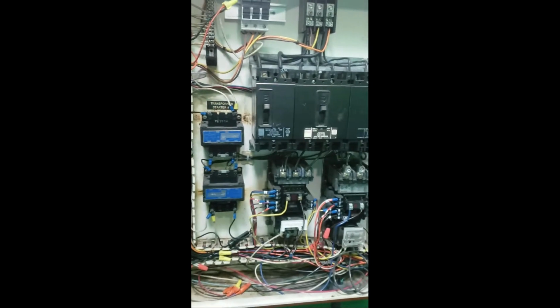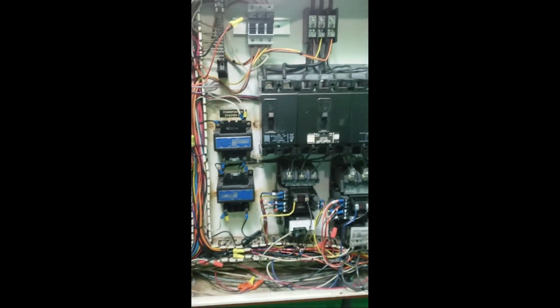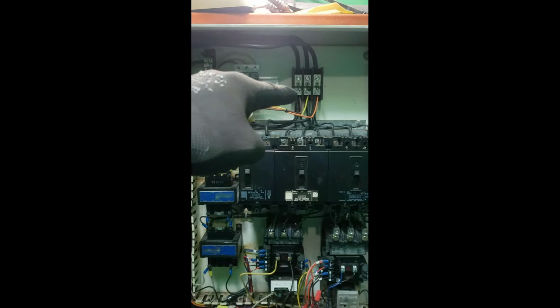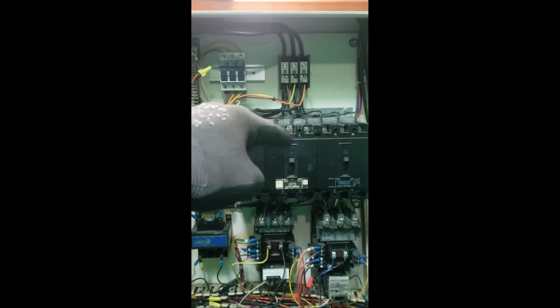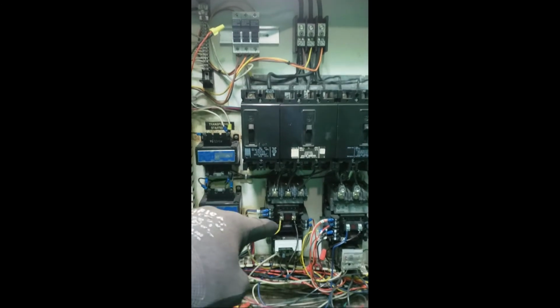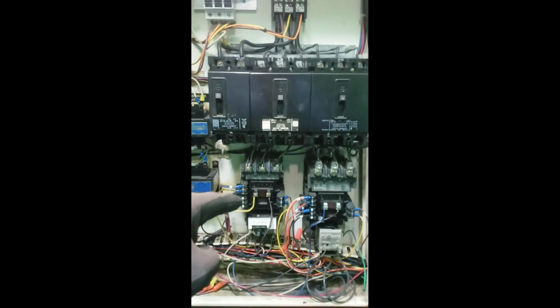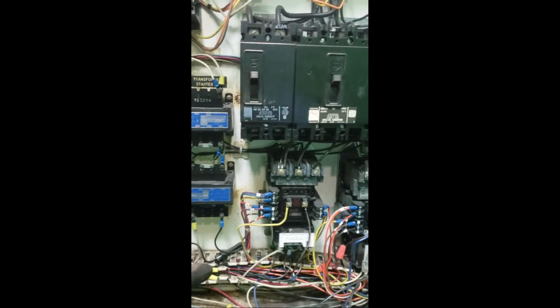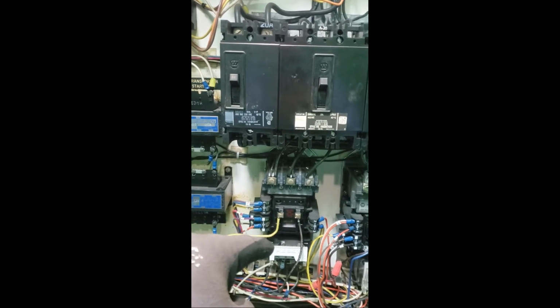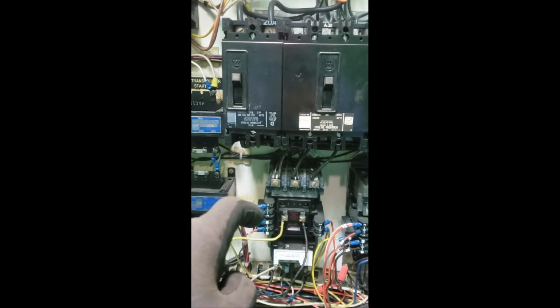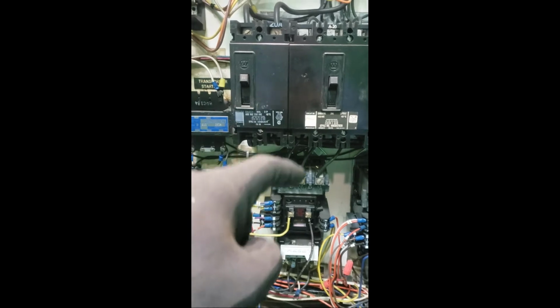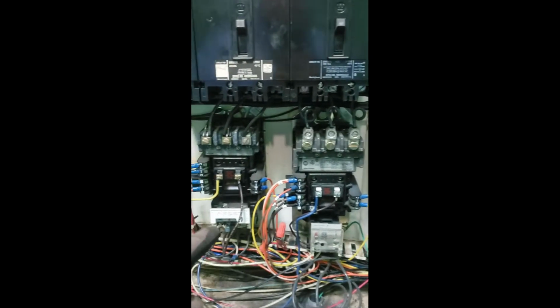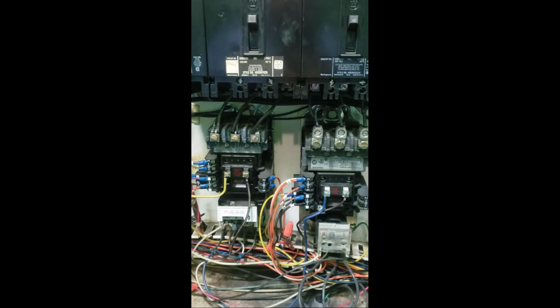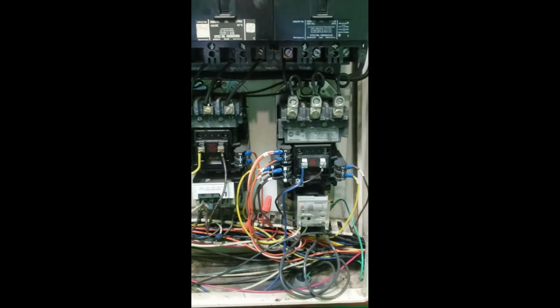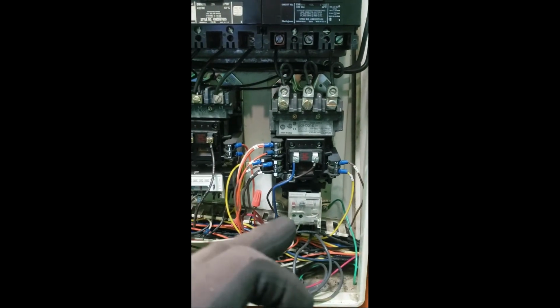But this is our motor control center. We've got our power coming in, and then it's distributed to the two breakers for pump 1 and pump 2. It goes down to the contactor - these are the switches that turn the pump on. Once electricity is applied to the coil, that energizes the coil and sends power to the motors. At the bottom down here, these are the overloads - so if the pump is pulling too many amps, to prevent it from overheating, these will trip.